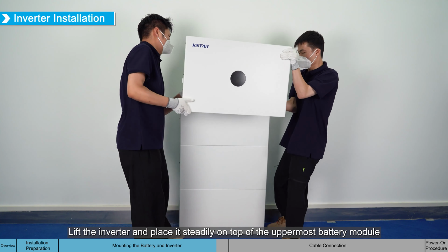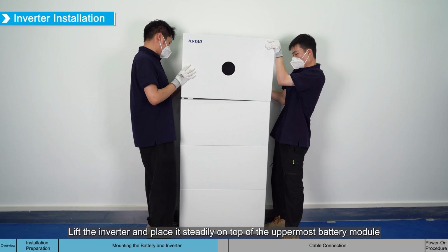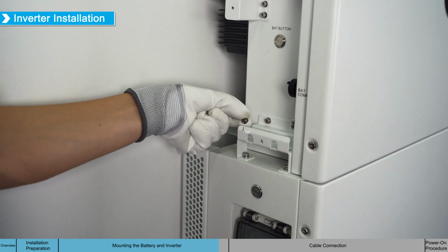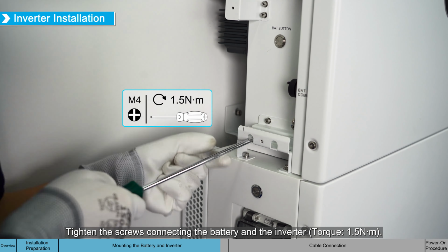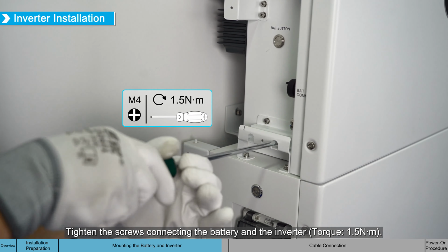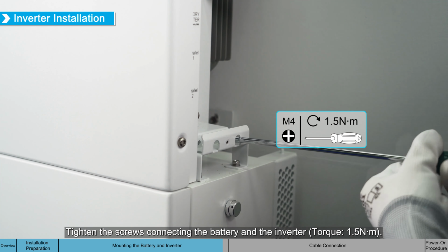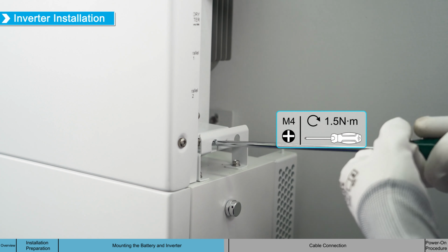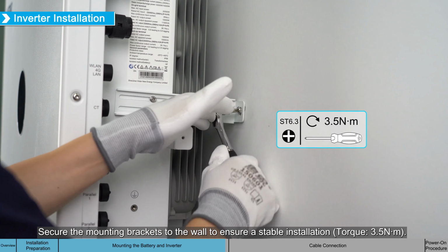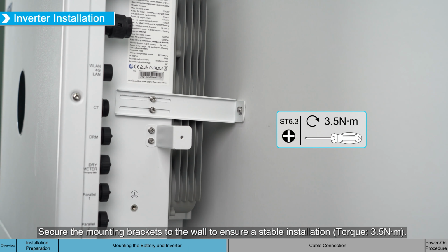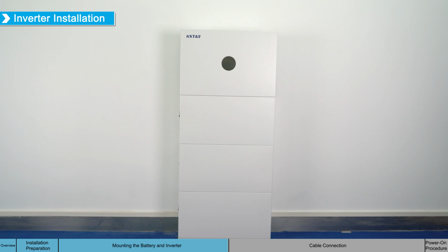Lift the inverter and place it steadily on top of the uppermost battery module. Tighten the screws connecting the battery and the inverter. Torque, 1.5 Nm. Secure the mounting brackets to the wall to ensure a stable installation. Torque, 3.5 Nm.